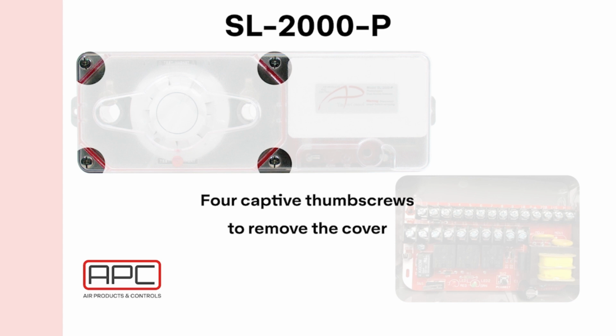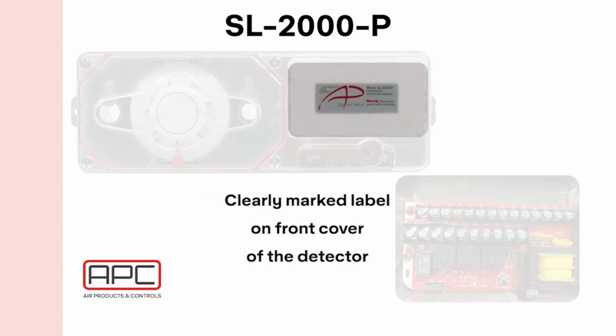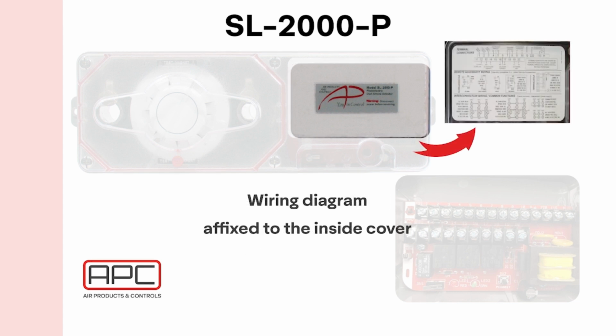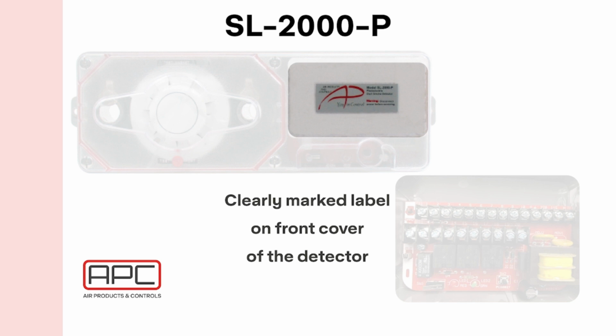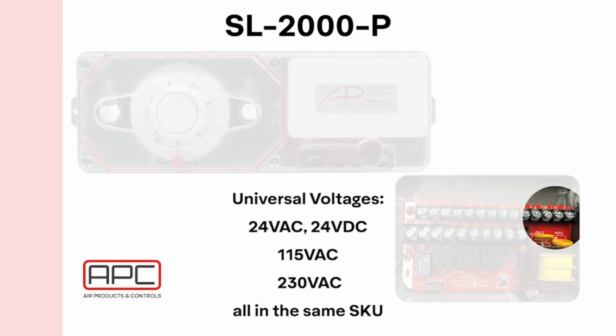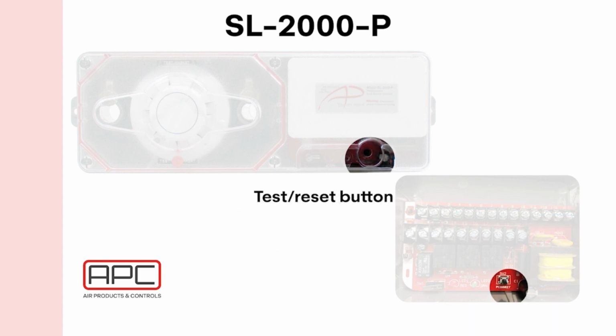The label, including the brand, model, and sensor type, is located on the front cover. The wiring diagram is affixed to the inside cover, which saves time for the installers and servicing technicians. Universal voltage, including 24 volts AC, DC, 120, and the higher range of 230, is available all in one SKU. A test and reset button is available to reset the unit with the cover on.